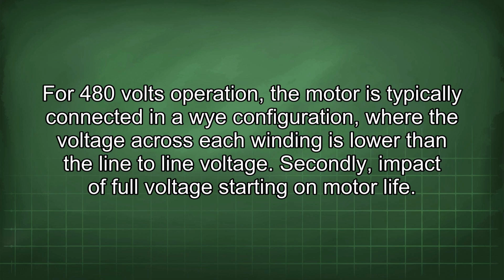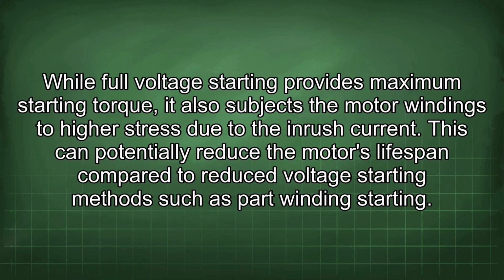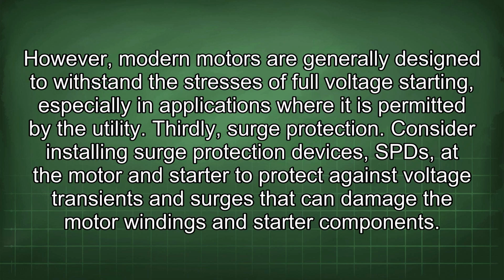Secondly, impact of full voltage starting on motor life. While full voltage starting provides maximum starting torque, it also subjects the motor windings to higher stress due to the inrush current. This can potentially reduce the motor's lifespan compared to reduced voltage starting methods such as part winding starting. However, modern motors are generally designed to withstand the stresses of full voltage starting, especially in applications where it is permitted by the utility.